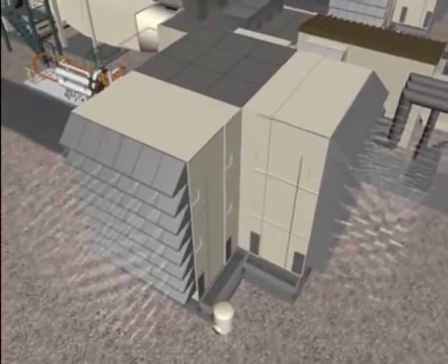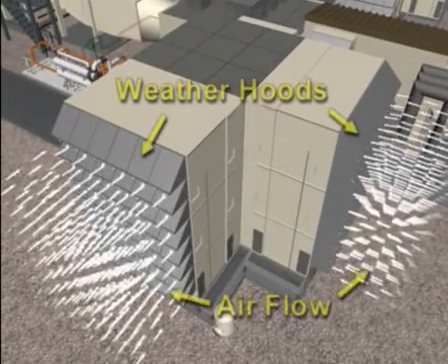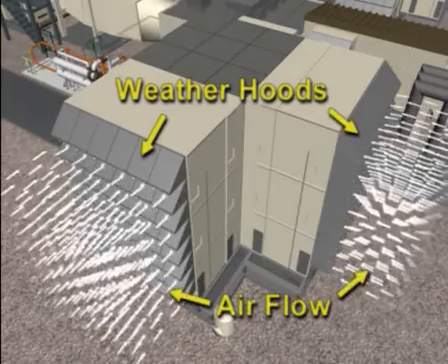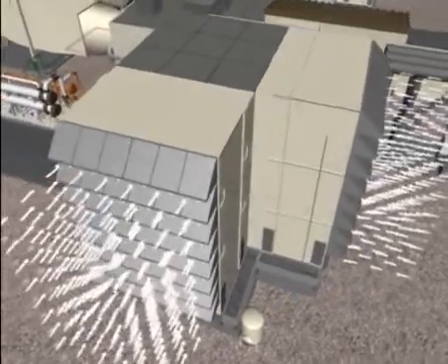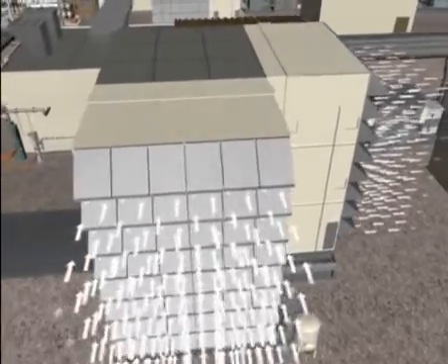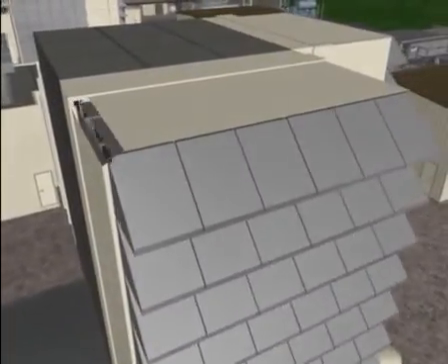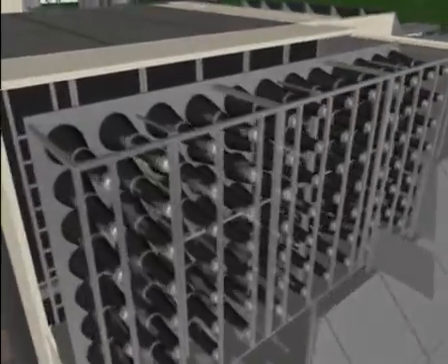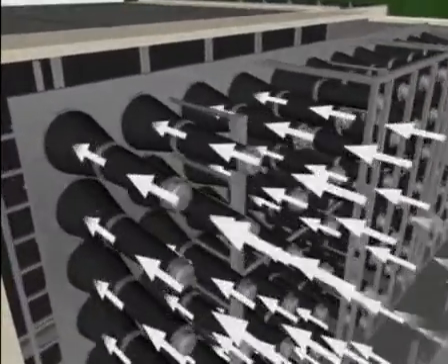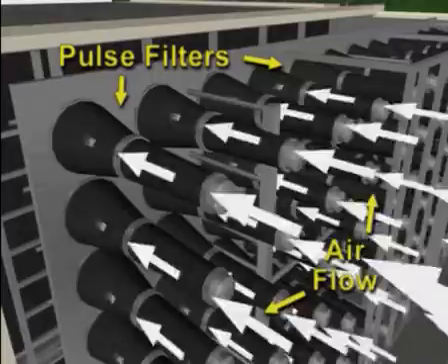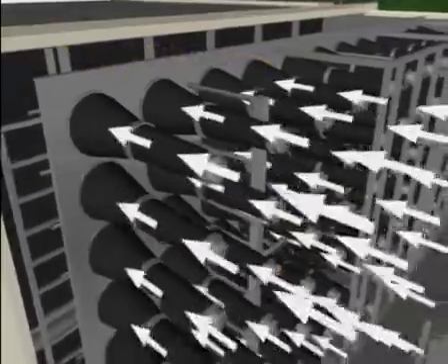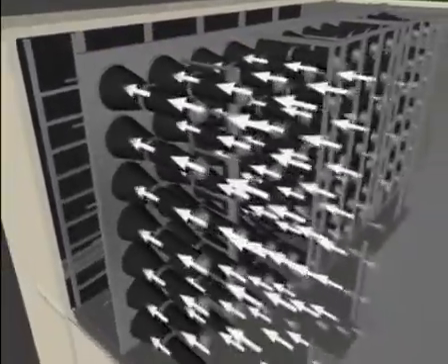The incoming air to the combustion turbine first goes through a weather hood to a filter housing. The weather hoods protect the filters from the effects of rain and sun and help minimize the amount of debris drawn into the filters. The air is drawn into and through the filter canisters. These filters remove particulates from the incoming air before it is admitted to the compressor inlet.